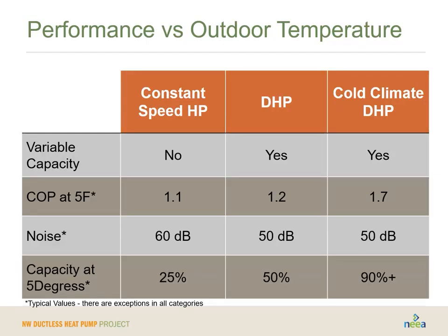Other ways to look at this: ductless heat pumps are what we call variable capacity. That means they can slow down both their ability on the compressor side to produce heat as well as the indoor fan to move air. They can slow down and operate at something like 25 or 30 or 40% of their total design capacity for long periods of time and still produce work. Your old school big compressor air source heat pump, the one that you may be familiar with in terminology, typically is not variable capacity, meaning it runs at one, maybe two speeds. With that, it means they're louder. They do not have as high of a COP, or coefficient of performance. And that constant speed heat pump really is not able to produce a lot of capacity at 5 degrees.